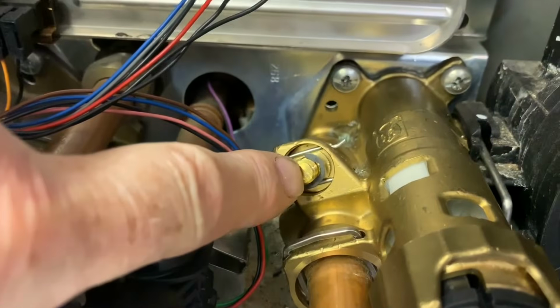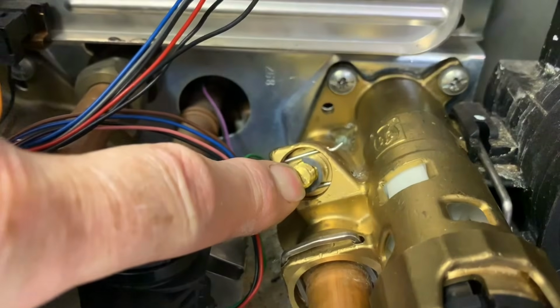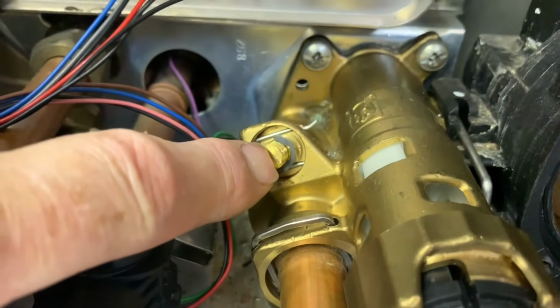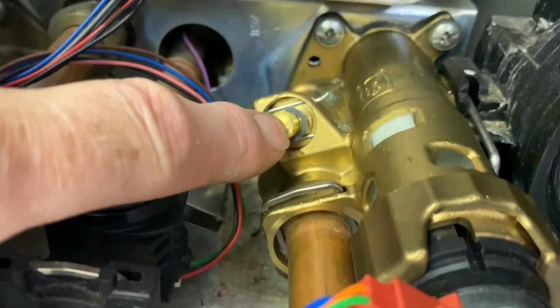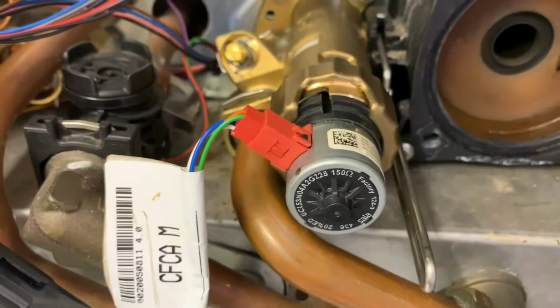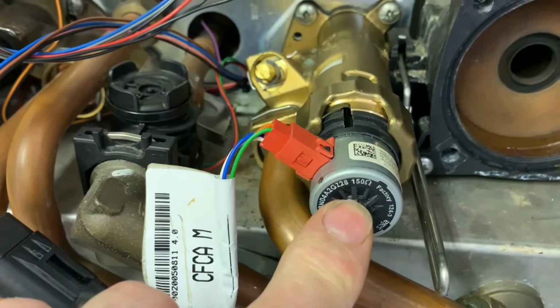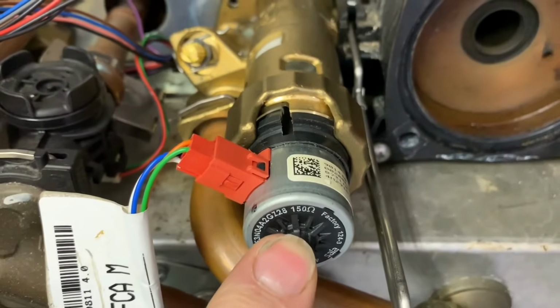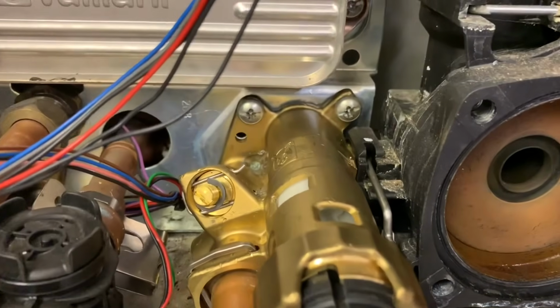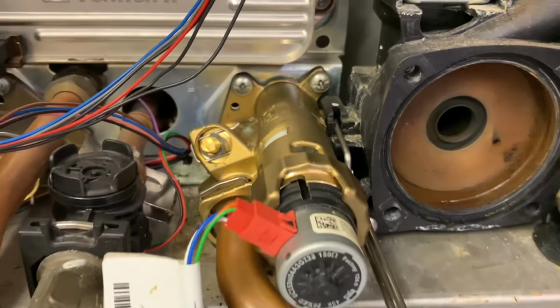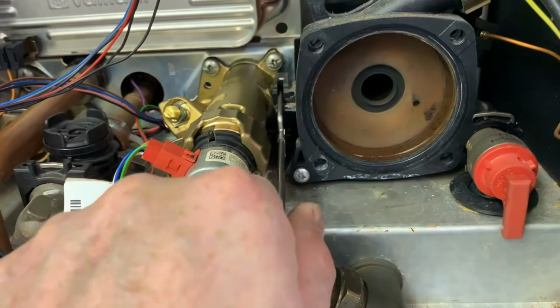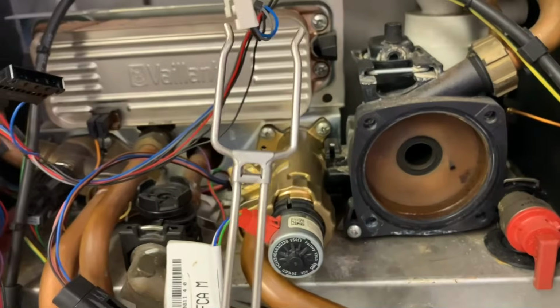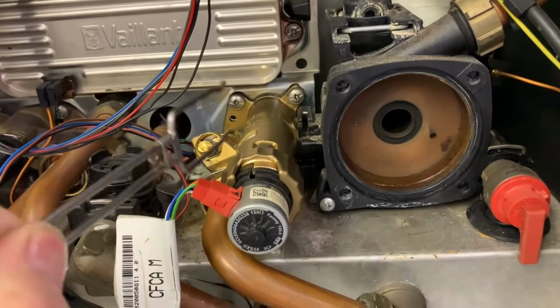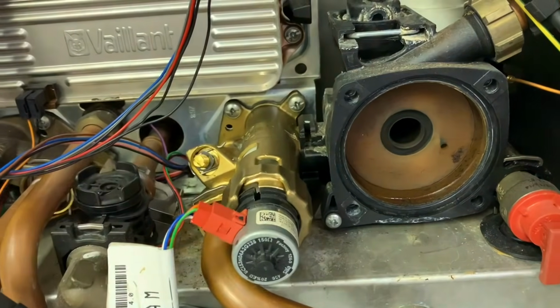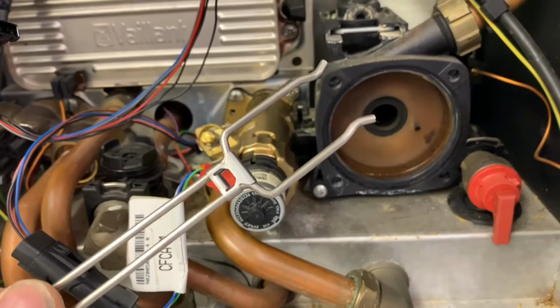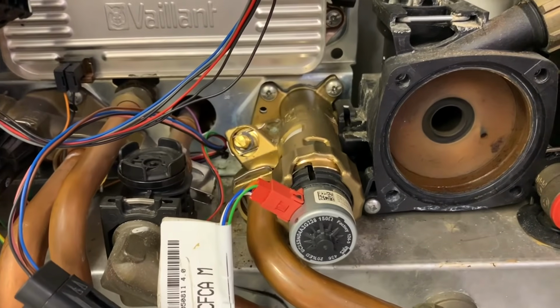This, what you can see here, is the automatic adjustable bypass. When we take the diverter valve off, you'll see where that connects onto. And this is the head, the motor. We're going to strip that off to have a look at that. So first thing to do is get these 3 screws out. So we also need to remove this, which is a clamp which holds the diverter onto the pump body. So that's out now. Let's get these screws out and let's get it stripped.